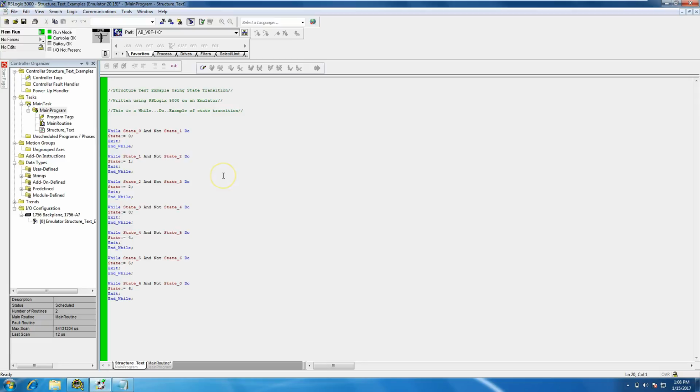So not to get off topic, anyway, this is how you program a while do. Note the exit is important, and the exit is important to show the infinite loop scenario. So you don't want to get caught in an infinite loop. You want to make sure you shut the while do function off. Make sure it exits out, or it's going to steady keep going like in here, actually faster than the processor can handle. So it will fault, or it can fault.